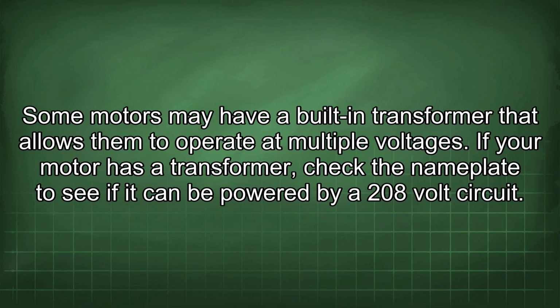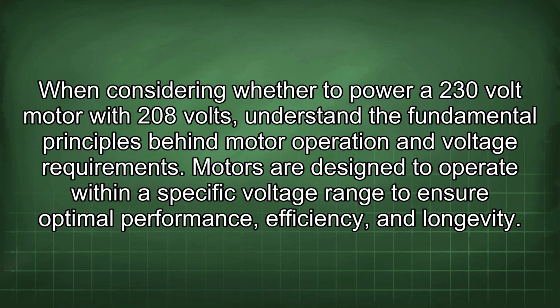Some motors may have a built-in transformer that allows them to operate at multiple voltages. If your motor has a transformer, check the nameplate to see if it can be powered by a 208-volt circuit. When considering whether to power a 230-volt motor with 208 volts, understand the fundamental principles behind motor operation and voltage requirements. Motors are designed to operate within a specific voltage range to ensure optimal performance, efficiency, and longevity.